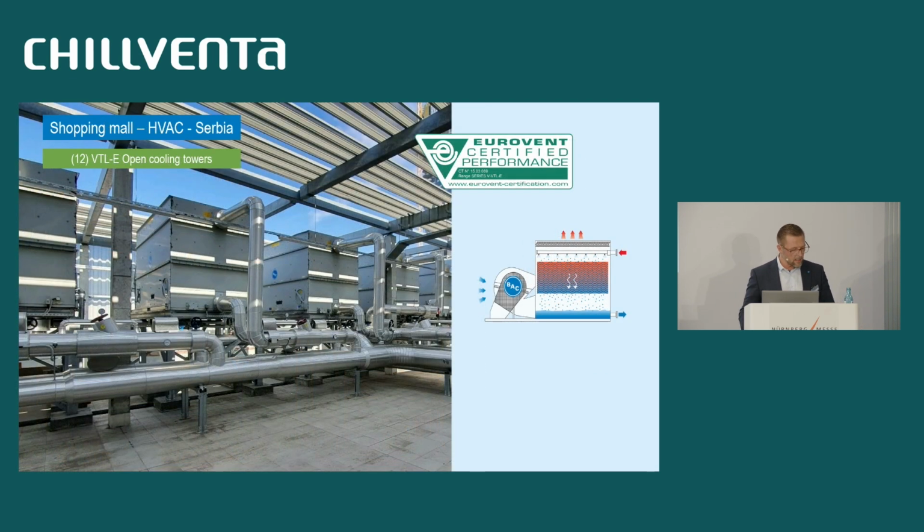Here is a shopping mall in Serbia, where again open cooling towers are installed. These are so-called low-profile cooling towers with centrifugal fans. Those coolers have again the same advantages as the previous. The motor and the fan are at the bottom and easy to reach. This VTLE unit has a very low height and is often chosen for indoor installations or roof installations at public buildings, as it's not visible from the ground.